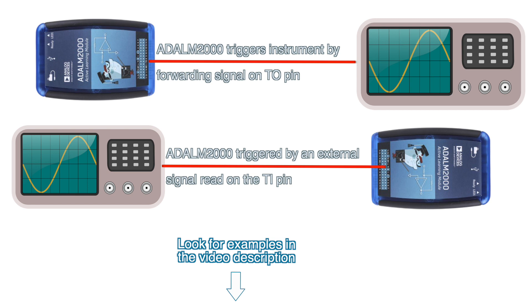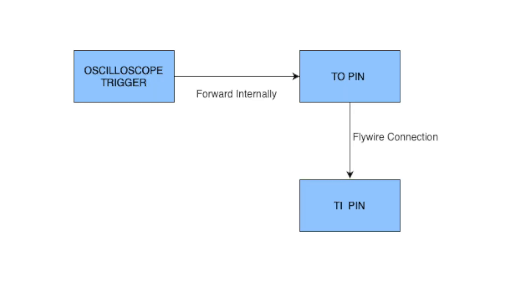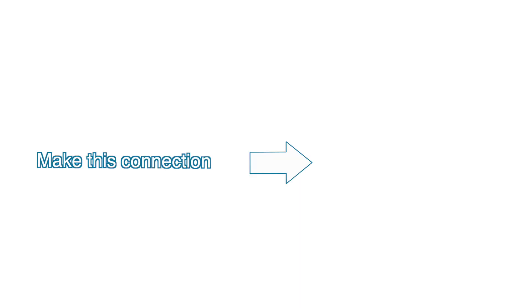On the other hand, you can use the TI pin to trigger an ADALM2000 module with an external signal. We'll demonstrate the principle of operation by forwarding the oscilloscope trigger on the TO pin, which will connect to the TI pin. Then we'll set the logic analyzer to be triggered on the external trigger in. Connect the TI and TO pins.